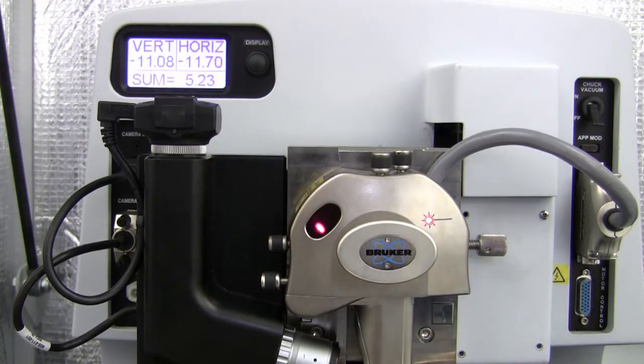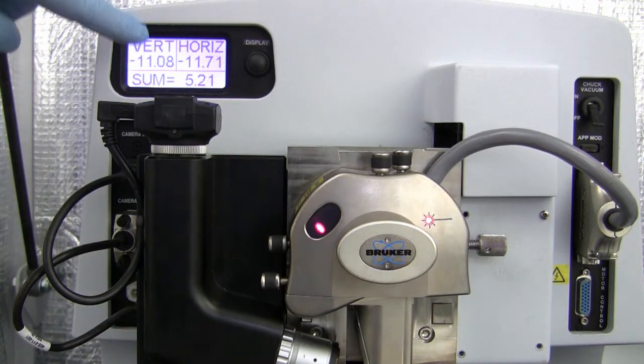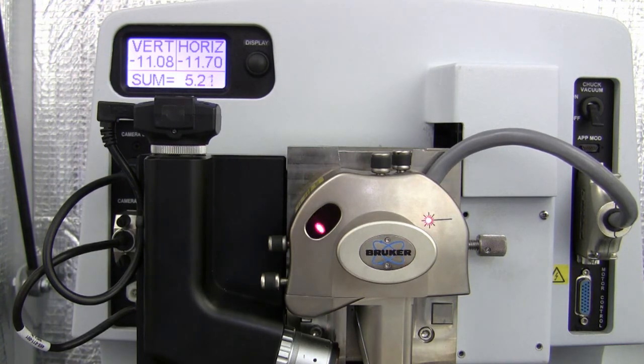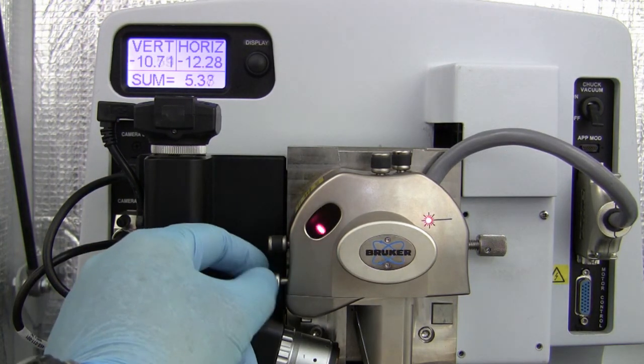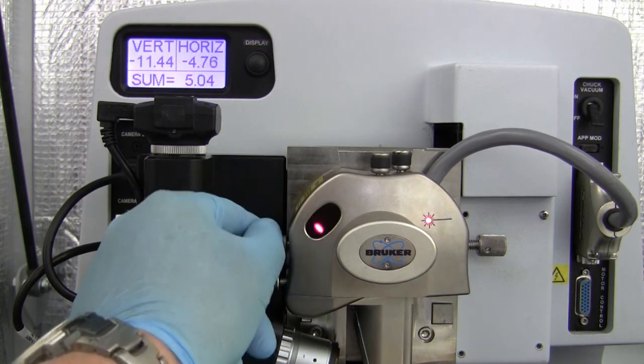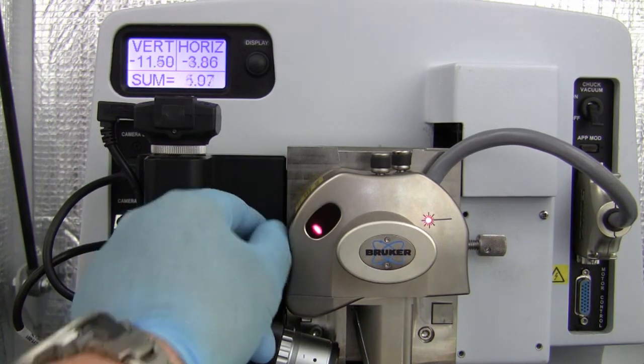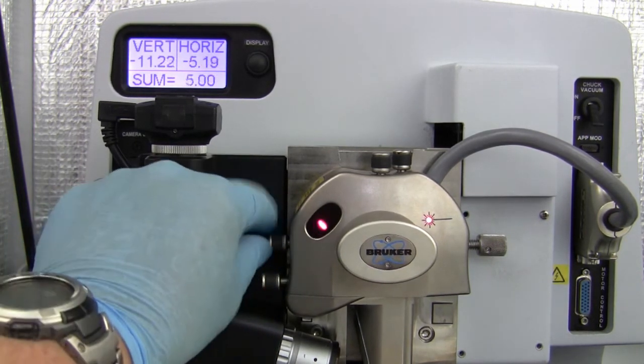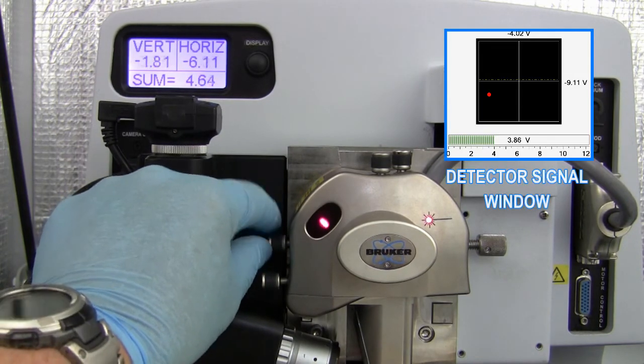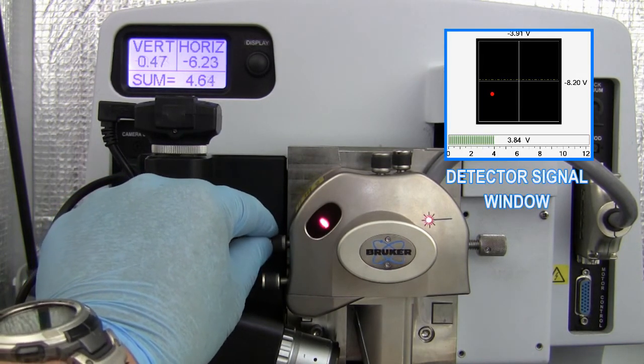The LCD screen on the stage and the software detector signal window will display the numeric value of the detector output. The intention is to balance the top versus bottom signal as well as the left versus right so that the laser is as close to the center of the detector as possible. This will result in the top, bottom, and left-right signals approaching zero.